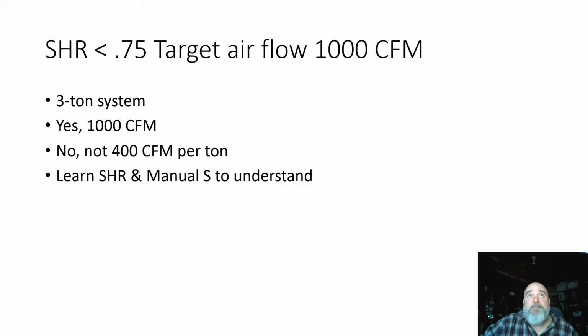We ended up with a sensible heat ratio of under 0.75. And the way you calculate your sensible heat ratio is to take your total BTUs and divide them into your sensible BTUs. And based on our sensible heat ratio, Manual S gives us guidance to tell us what our airflow is supposed to be. It ends up being 1,000 CFM in our example here. And the example here shows that it ends up being a 3-ton system. And yes, a 3-ton system can be paired with 1,000 CFM to achieve the indoor conditions to which we are shooting for. 400 CFM per ton is not always the correct answer.